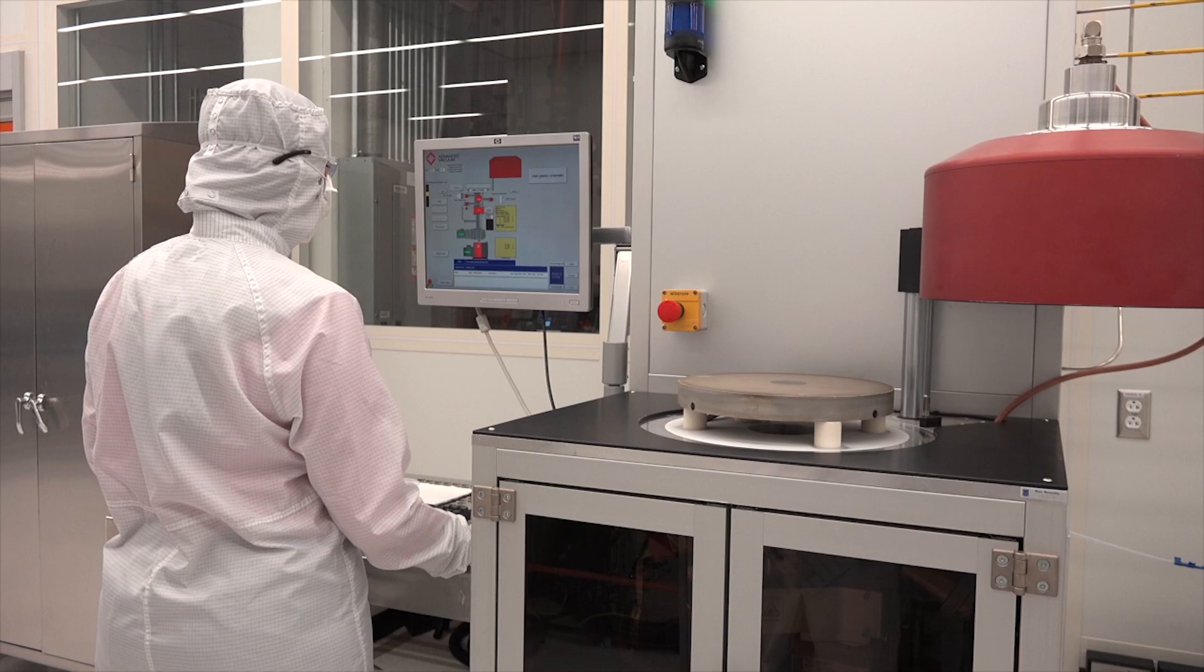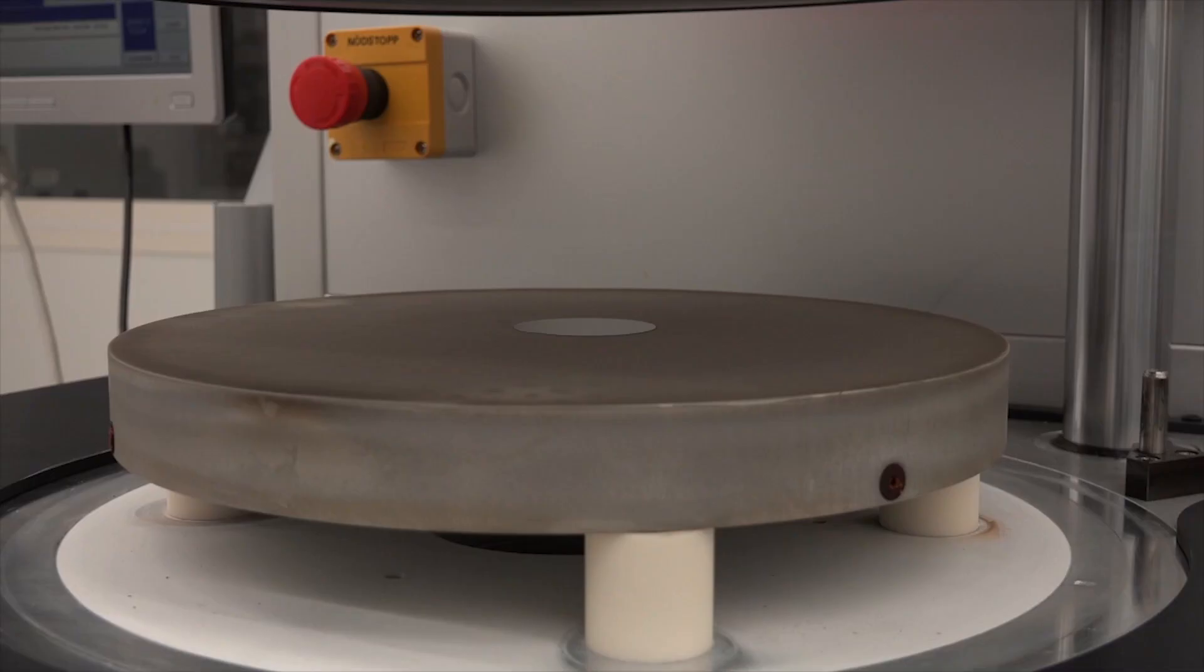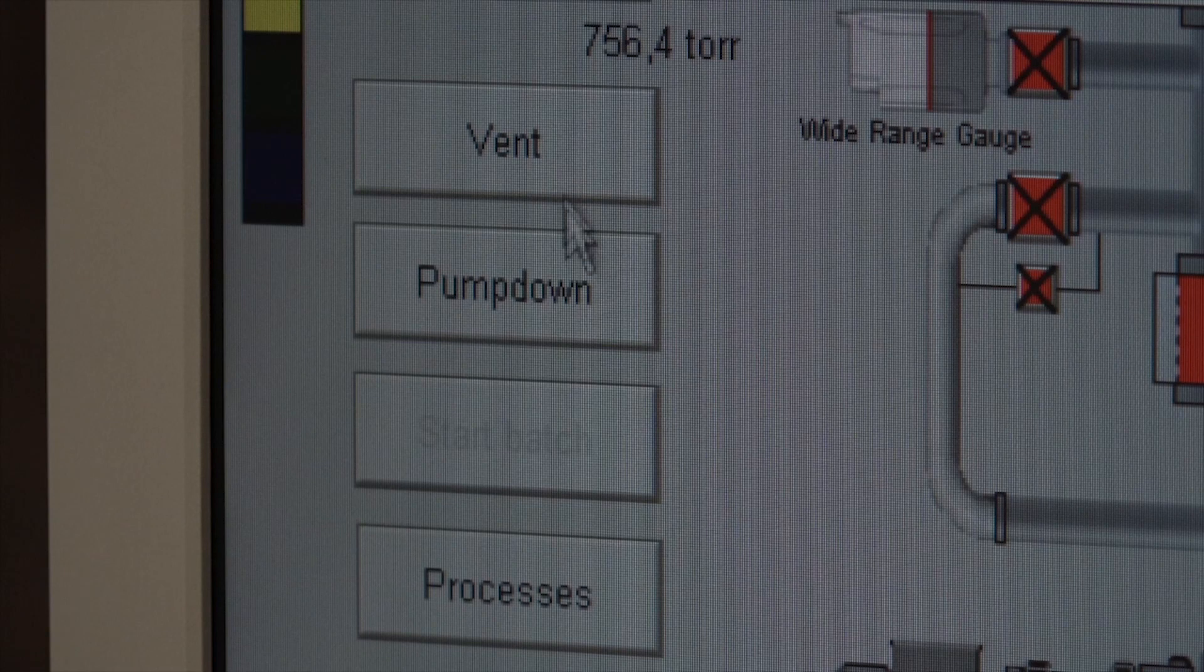With the sample in place, we can now close the chamber. We use the computer to do this. Now, we can start the pump-down sequence. The system will be rough-pumped to a pressure of about 1 times 10 raised to minus 3 torr.